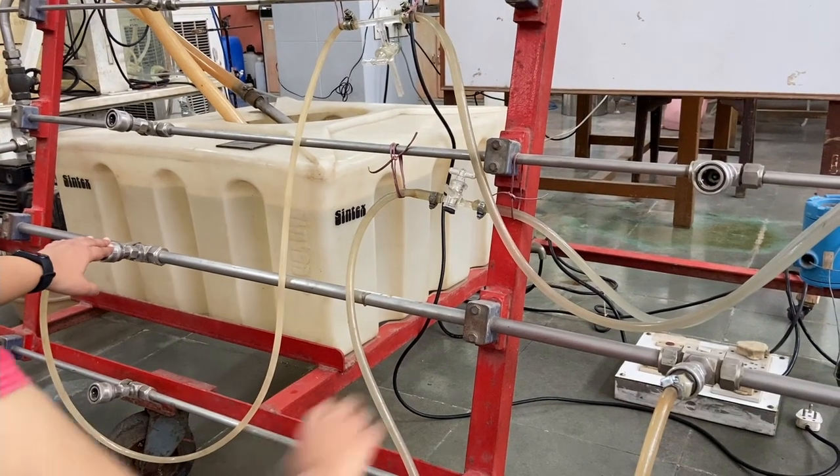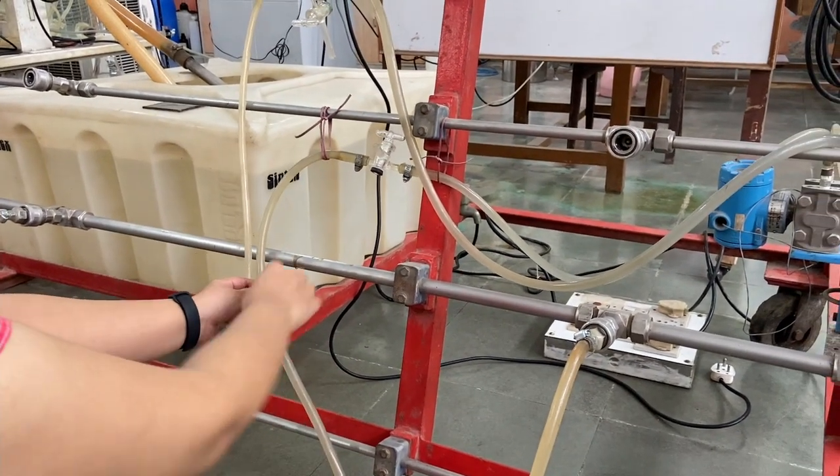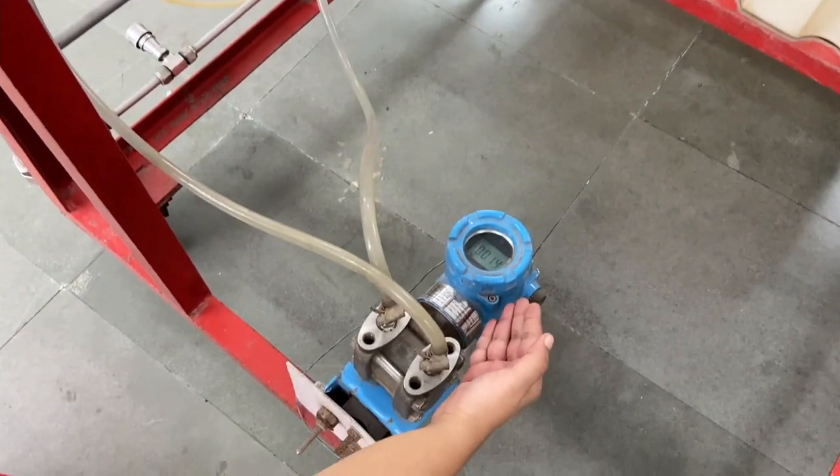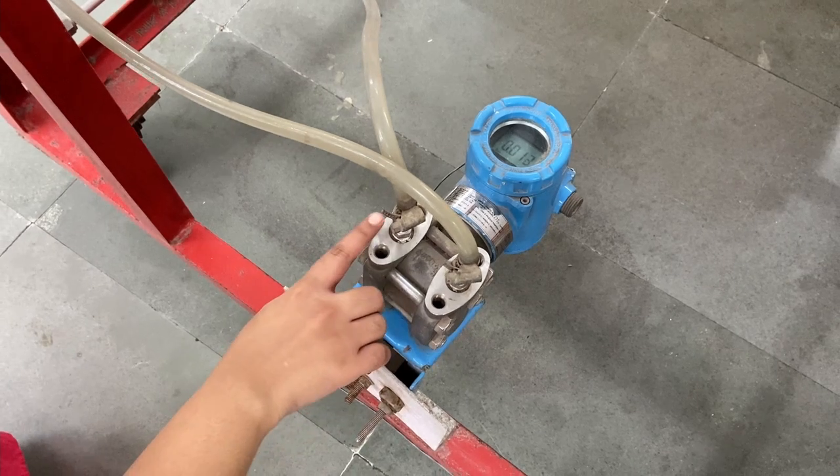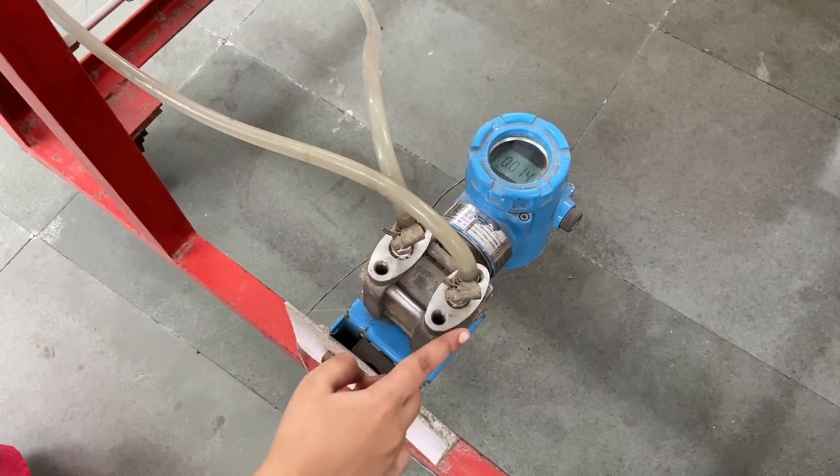The pressure drop across the two points in the pipes is measured using a differential pressure transducer. This instrument has a diaphragm as a sensing element placed between two ports which gets deflected by the applied pressure.